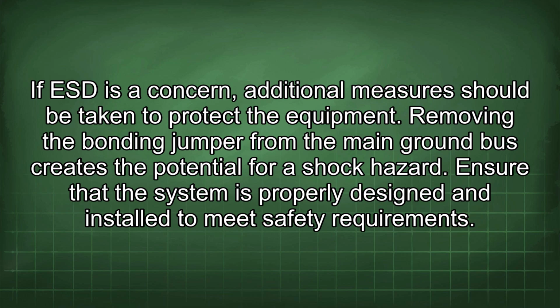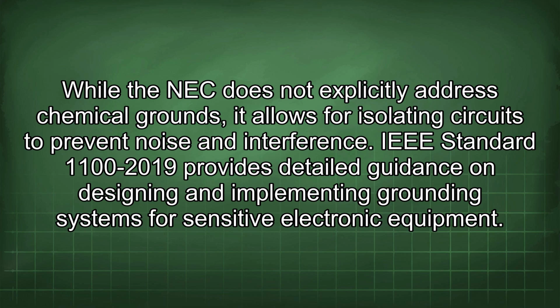Removing the bonding jumper from the main ground bus creates the potential for a shock hazard. Ensure that the system is properly designed and installed to meet safety requirements. While the NEC does not explicitly address chemical grounds, it allows for isolating circuits to prevent noise and interference.